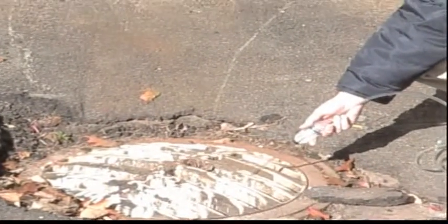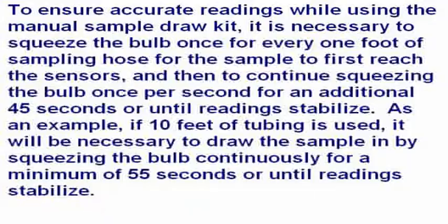In order to ensure that the sample is reaching the sensors, allow 1 squeeze of the bulb for every 1 foot of sampling hose. Continue to squeeze the bulb for an additional 45 seconds or until the gas readings stabilize, and note the gas measurements.